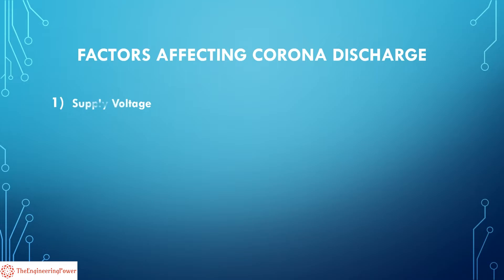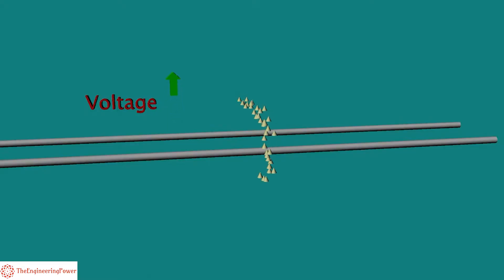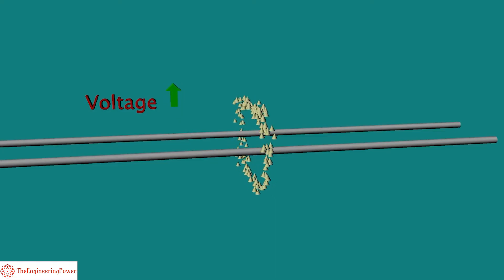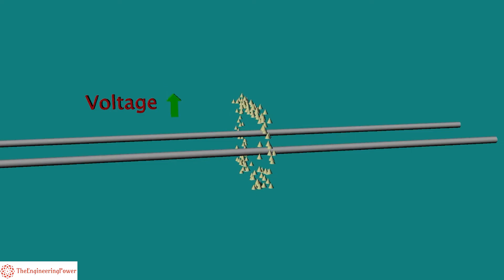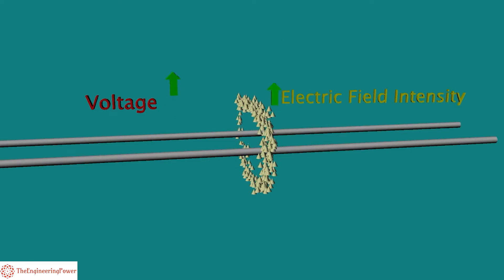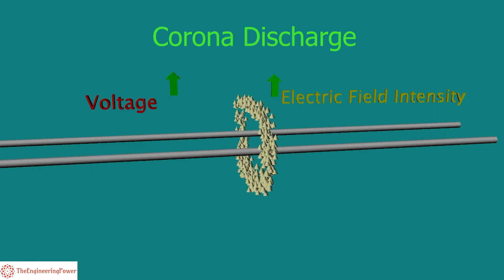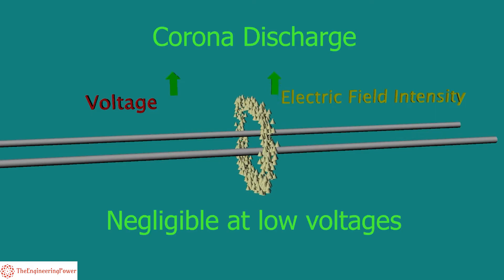The most important factor is the supply voltage. Corona discharge depends upon the electric field intensity produced by the system voltage. With increasing system voltage, the electric field intensity will increase, resulting in an increase of corona discharge. Corona discharge is negligible at low voltages.